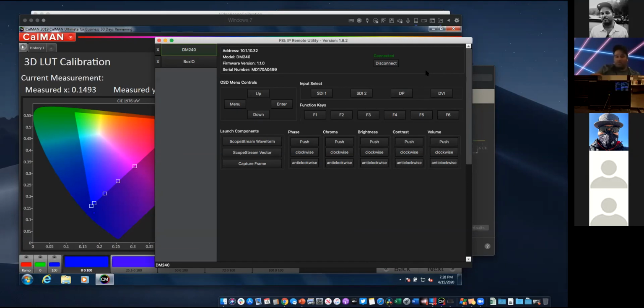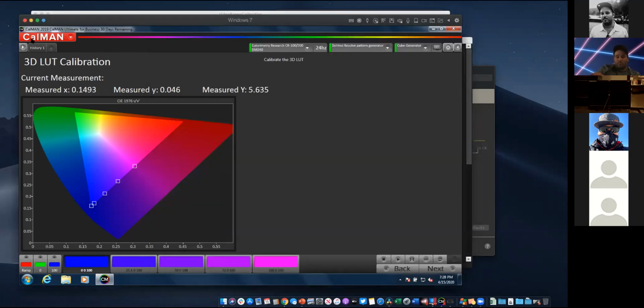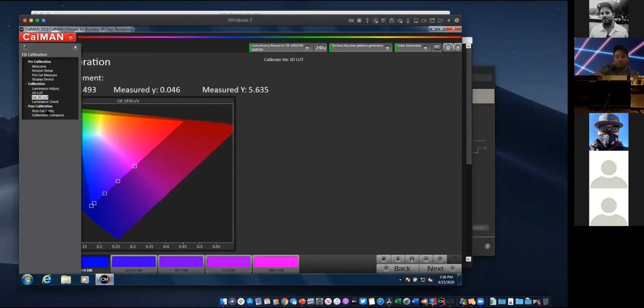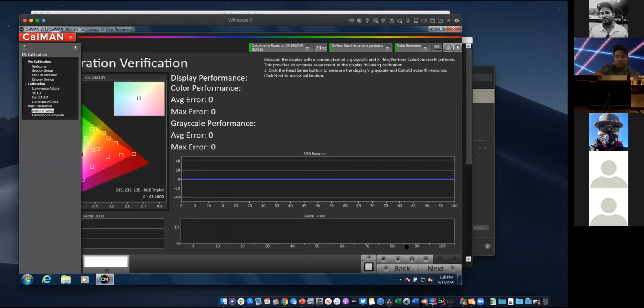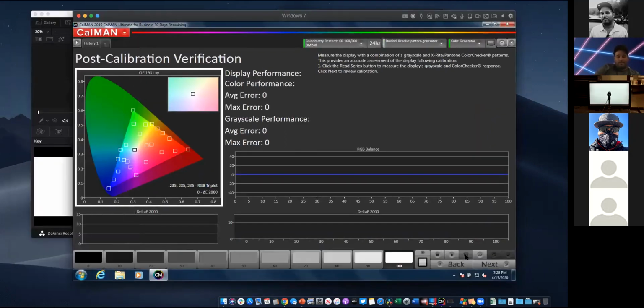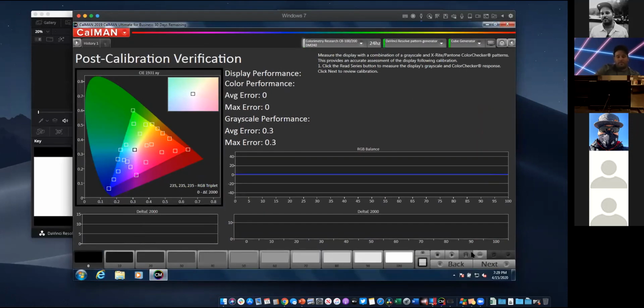Going to go bypass back to none. I'm going to go to the top of the color space menu and select user 3, which is where I saved it. And now I'm going to validate that result. And that's where this post-cal verify comes in. I'm going to select read series, and now it's basically going to see how the calibration was.